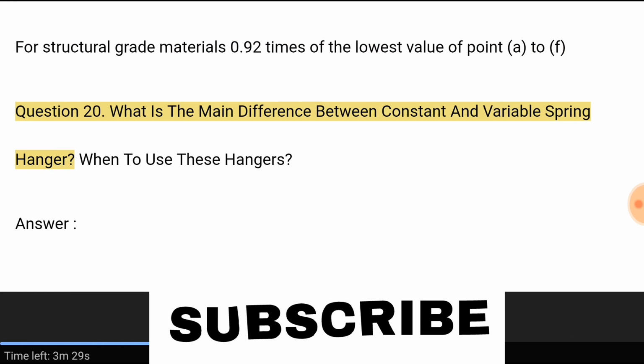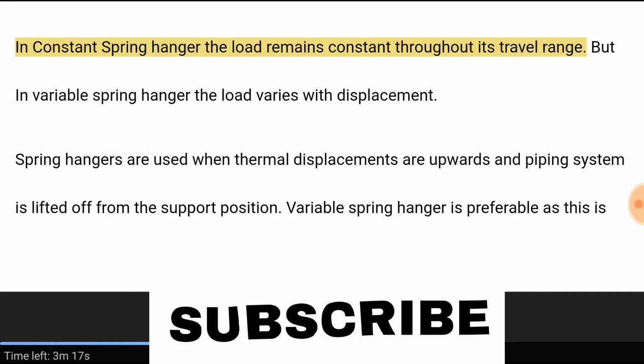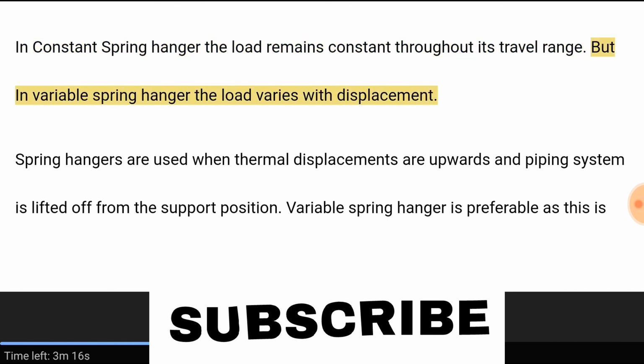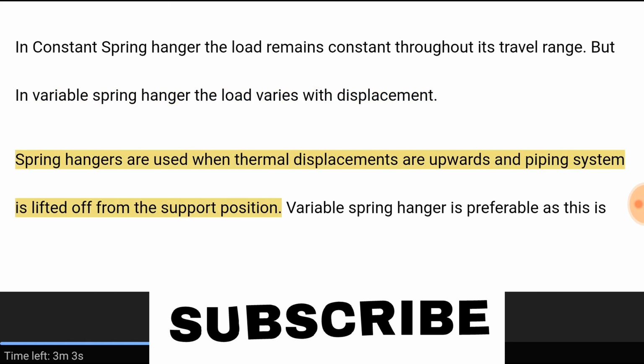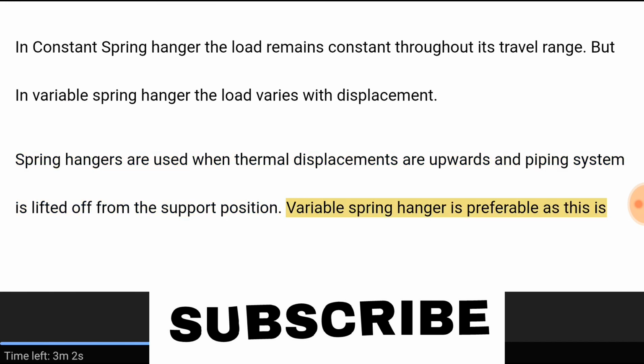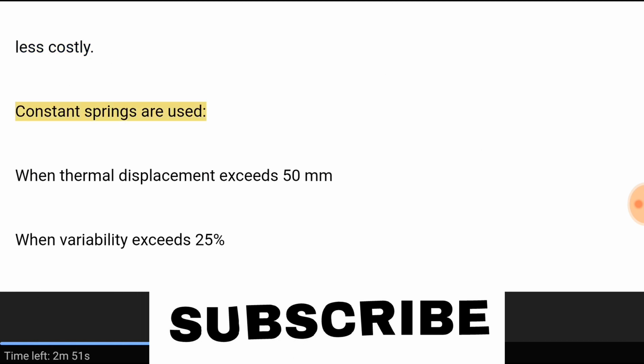Question 20. What is the main difference between constant and variable spring hanger? When to use these hangers? Answer. In a constant spring hanger, the load remains constant throughout its travel range. But in a variable spring hanger, the load varies with displacement. Spring hangers are used when thermal displacements are upwards and the piping system is lifted off from the support position. Variable spring hanger is preferable as this is less costly.